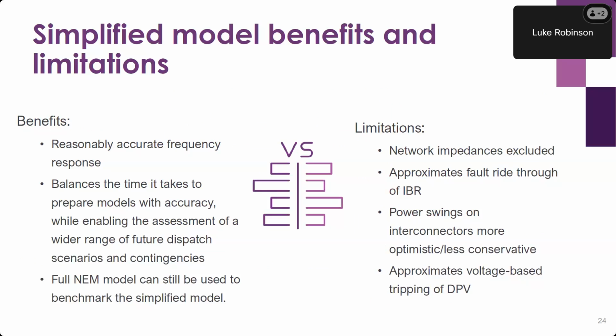On the benefit side, we've shown in benchmarking studies that it provides a reasonably accurate frequency response. So for studies where we're primarily interested just in the frequency, such as under frequency load shedding screening studies, this is going to be a lot easier to set up and redispatch cases for. In addition to this, benchmarking cases can be run in the full NEM model, just for a few cases, if we want to compare and understand the error margin.